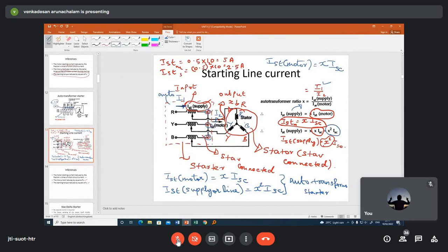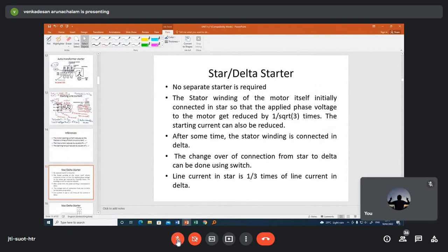People thought that instead of having a separate circuit, why can't we use the stator winding of the motor itself to act as a starter, so that it reduces the circuit complexity. That type of starter is called the star delta starter. This is very simple, and it came from the intelligent thinking of the people. You see here the motor stator winding itself, first it is connected in the form of star. It means that during starting time, the motor stator winding is connected in star, and during running time, using some switch, the same stator winding of the motor is connected in delta.